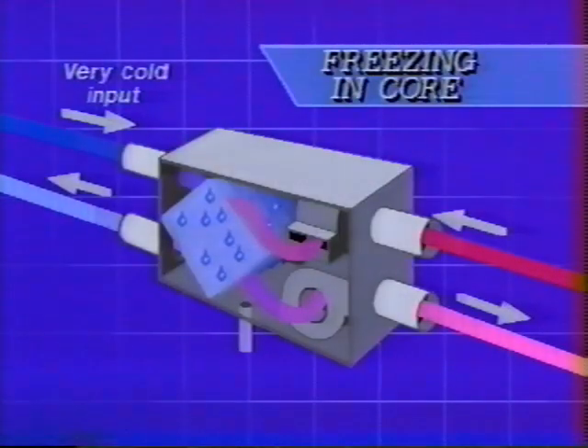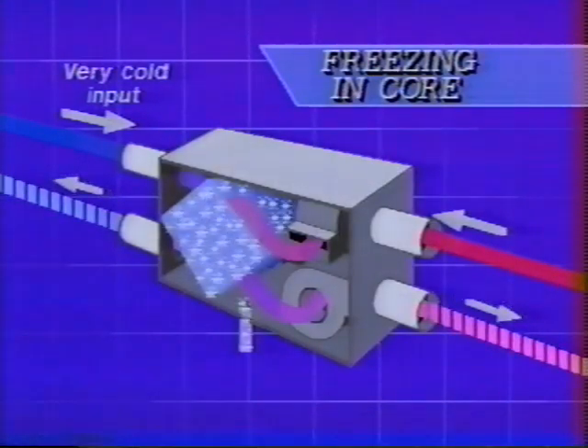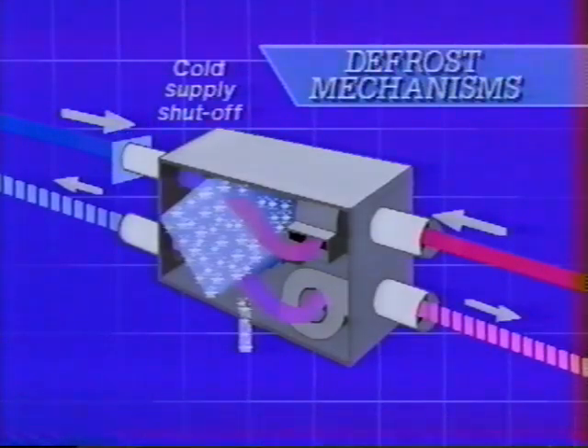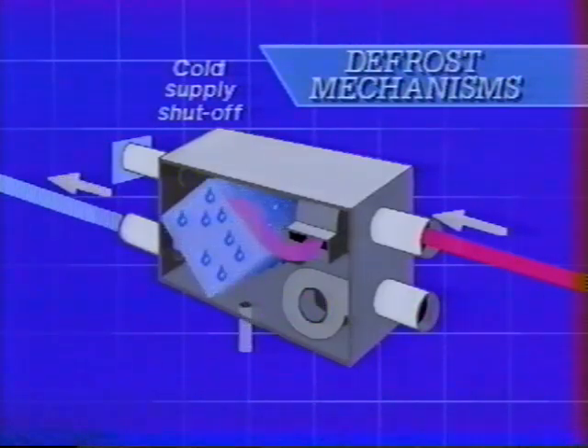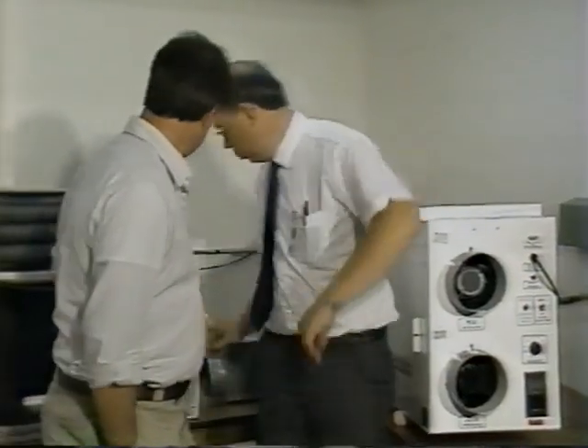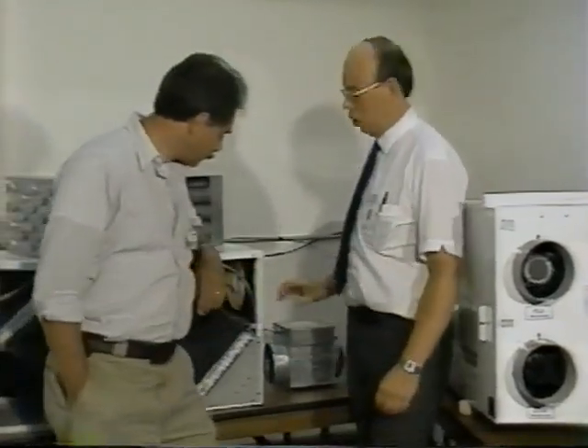That's right. There's a couple of different ways of doing the defrost. The first one on this unit is what we call a fan shutoff, where the cold outdoor air is actually stopped from coming in through the unit and the exhaust air is left running. What this does is heat up the core and allow any frost or ice to melt off and drain away. On this type of unit behind us, we have an electric preheat coil.